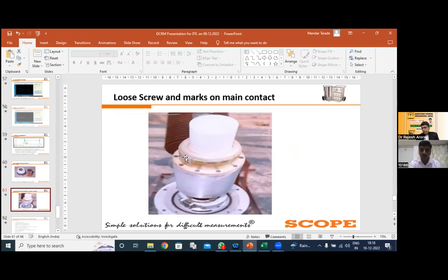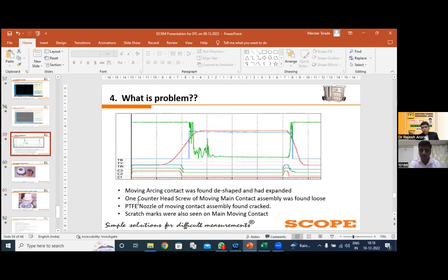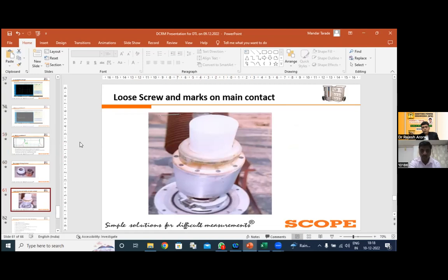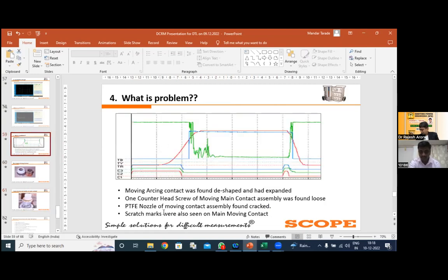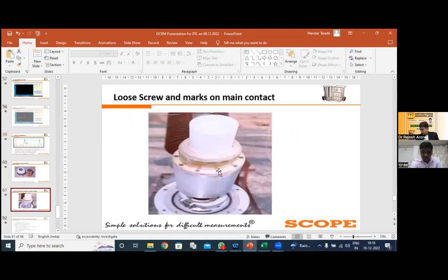Also, one more important thing is that I have particularly highlighted that one counter-head screw of the moving main contact assembly was found loose, and because of that, you see scratches on the moving contact. The scratches are clearly visible on the moving contacts. This we can identify because of the DCRM.